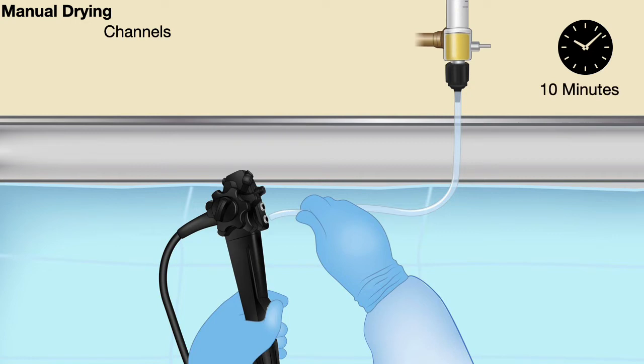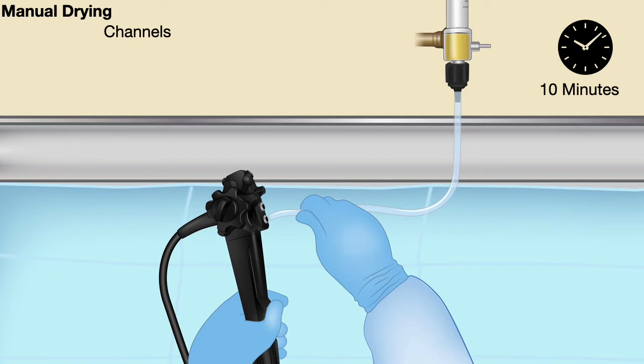The amount of pressure that should be used, one should follow the manufacturer's instructions for use. It is important to use 10 minutes of drying because studies have shown persistence of fluid in the channels with a drying cycle of less than 10 minutes.